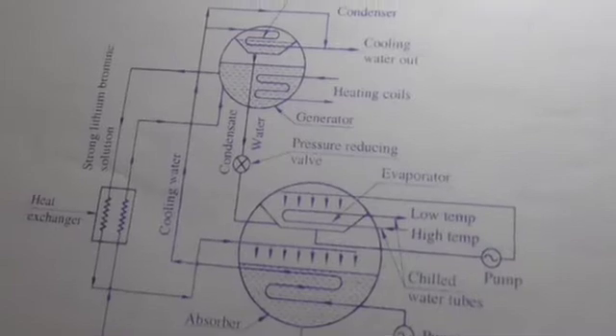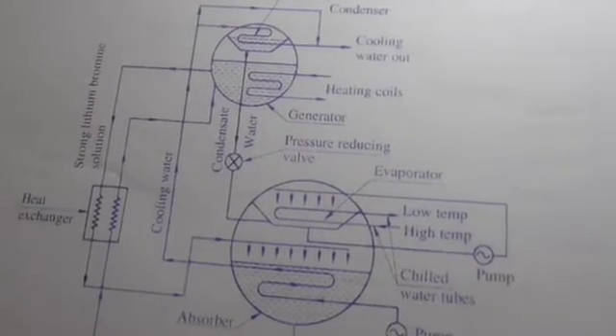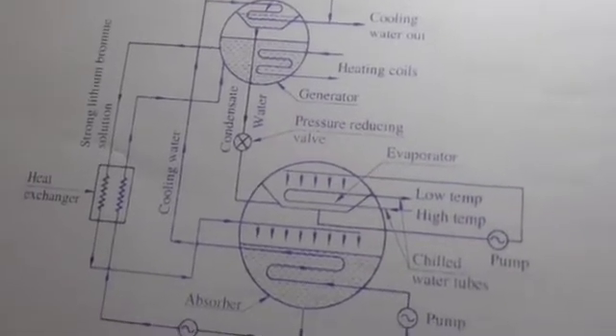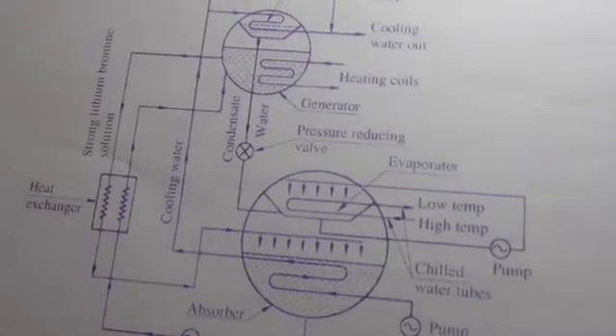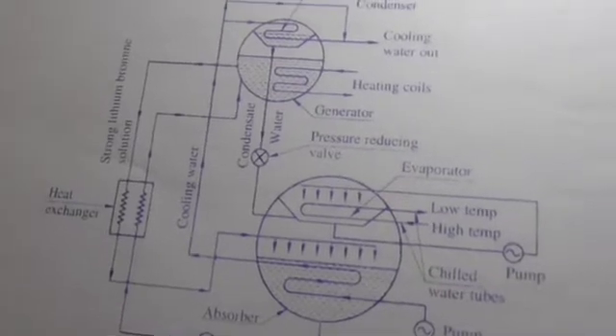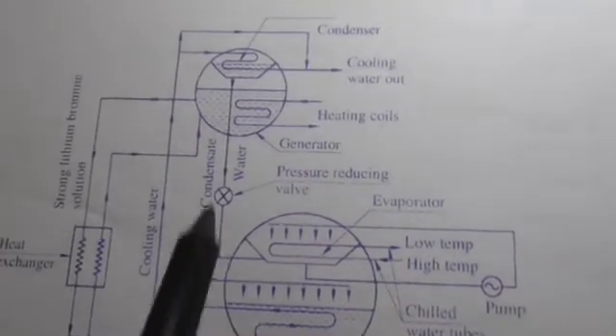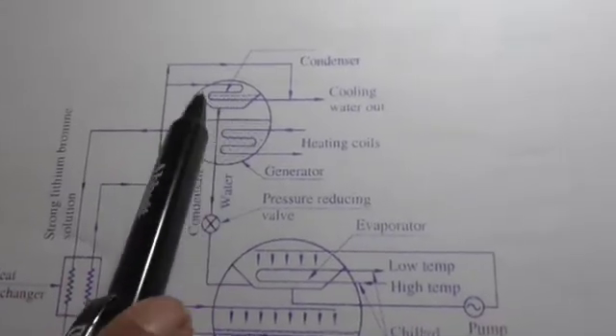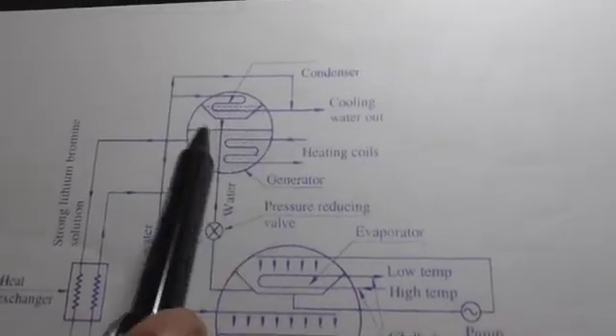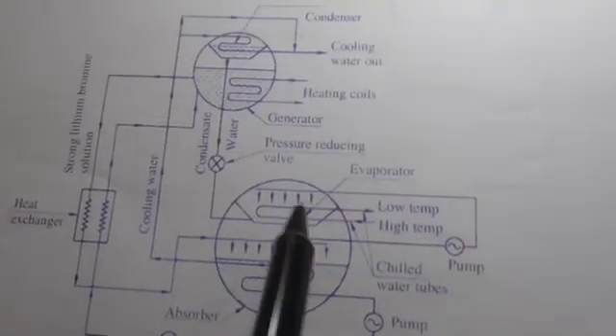Because lithium bromide is corrosive, lithium chromate is often used as an inhibitor — an additional salt added to the water. The absorber and evaporator are placed in one shell and operate at the same lower pressure. The condenser and generator operate at high pressure, while the absorber and evaporator operate at low pressure.